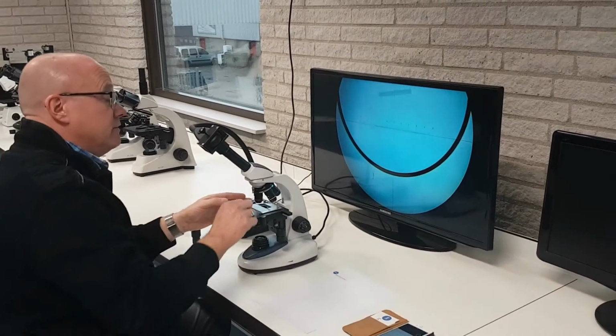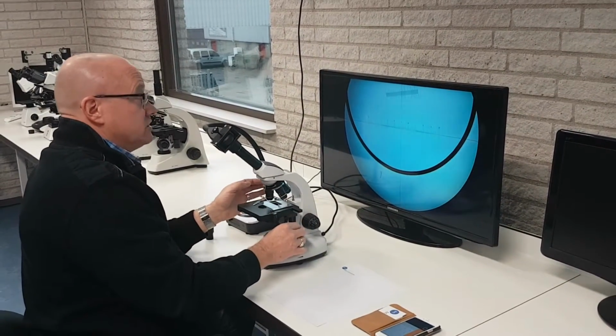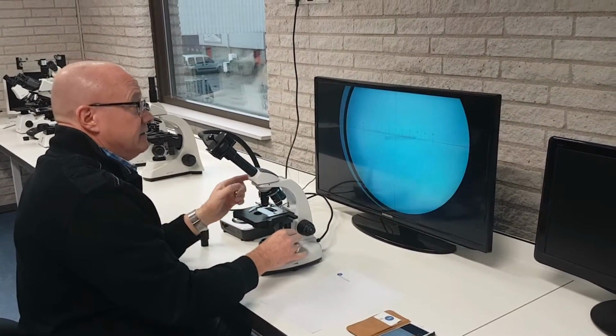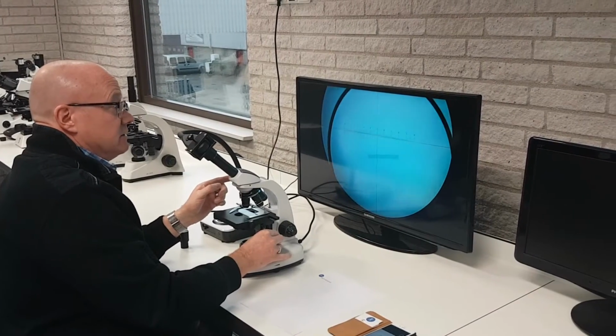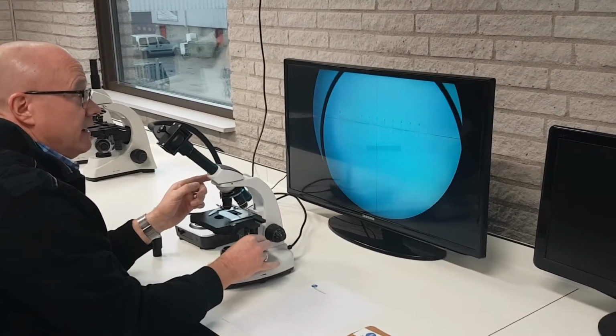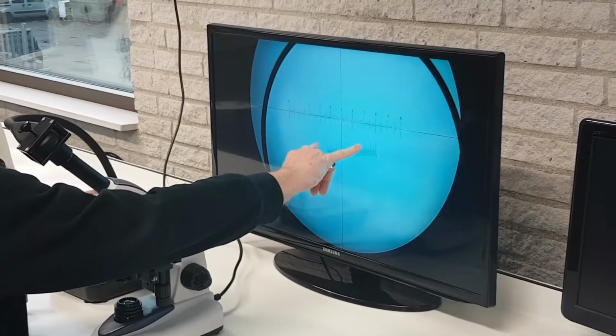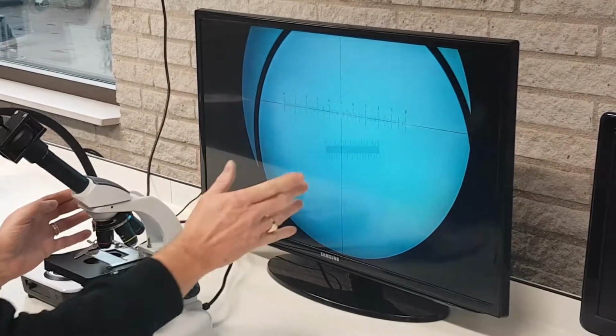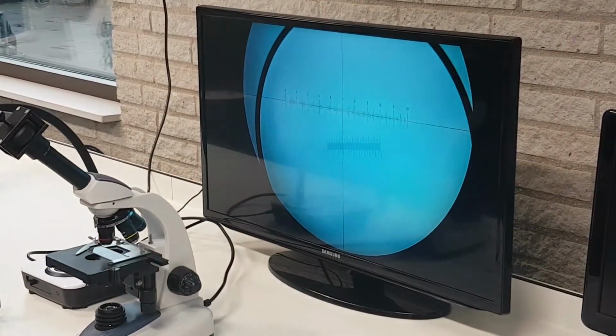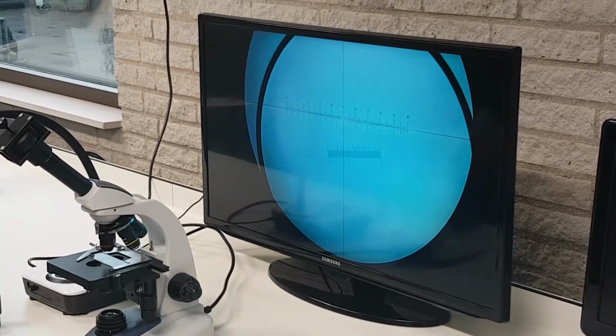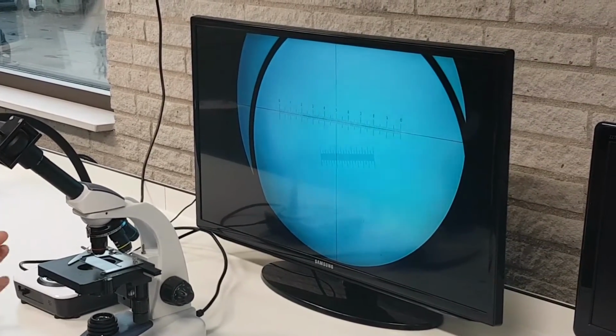To give it a unit, we put the stage micrometer on the stage, and you can see here, this is the stage micrometer that I move now, and this distance that you see here is exactly 1 millimeter. 1 millimeter is divided in 100 pieces. 1 millimeter is also 1,000 micrometers.